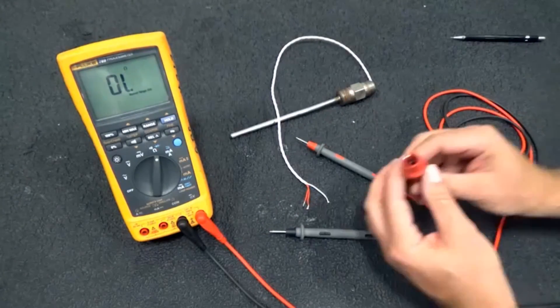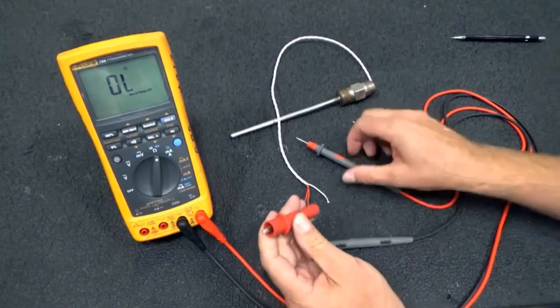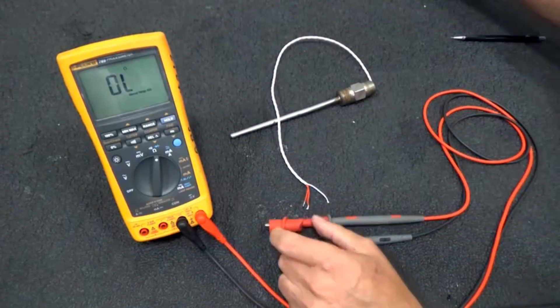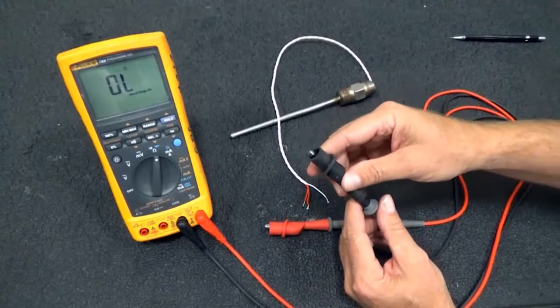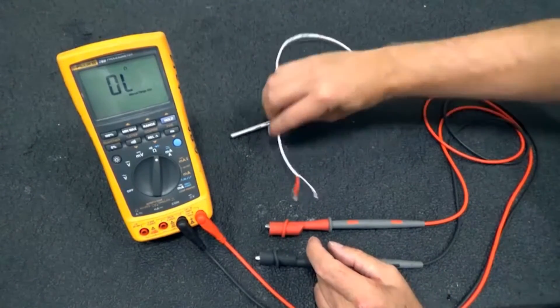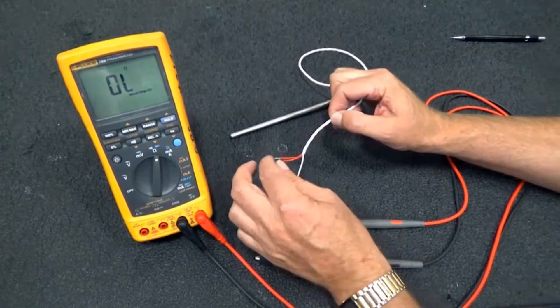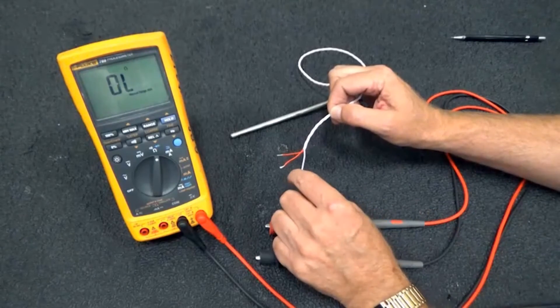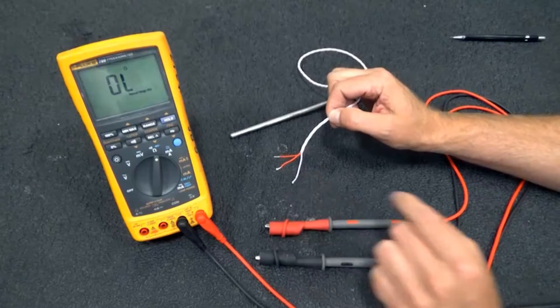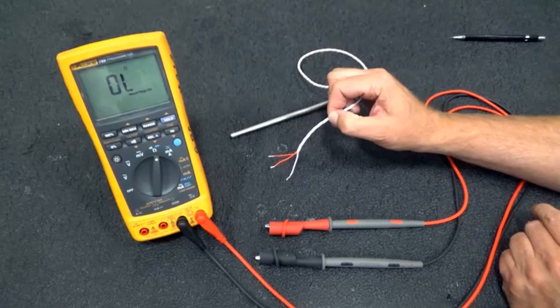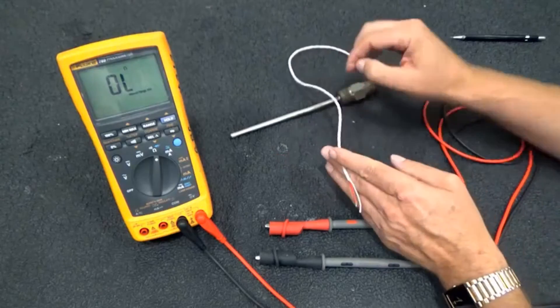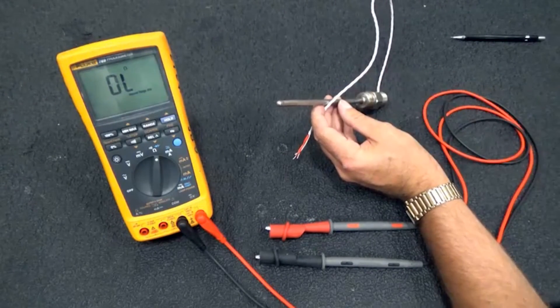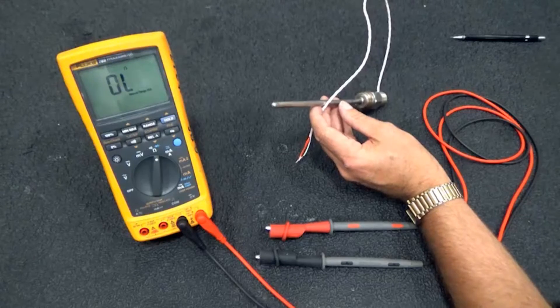I think what I'll do is I'm going to put on my alligator clips here so we can connect to the RTD without having to hold it with fingers. Like what we said before was that the red wires are connected together, and the white wire is on the other side of the resistor. The resistor is formed by a small piece of platinum wire that's down in the tip of this, and the resistance of that wire changes as temperature changes.